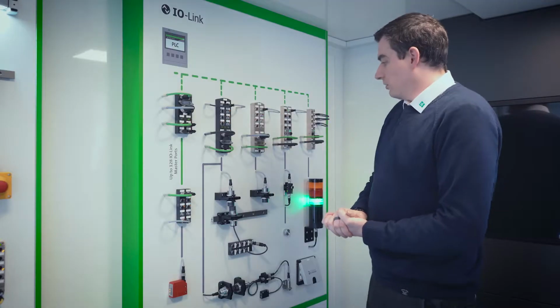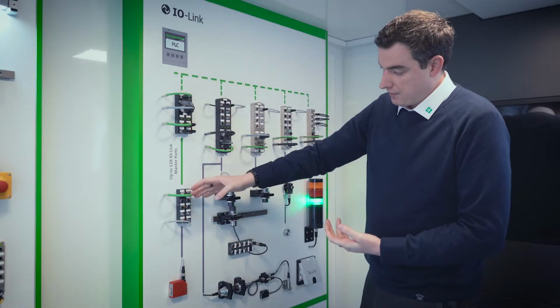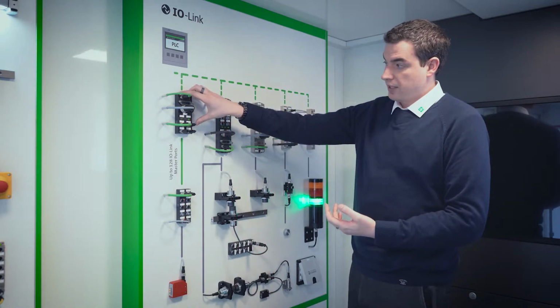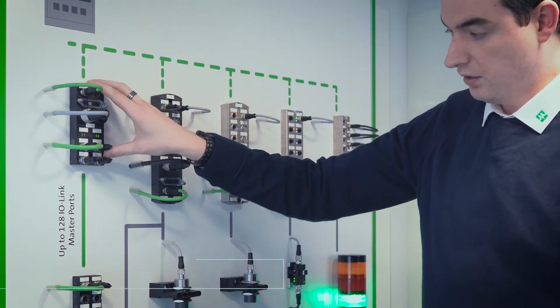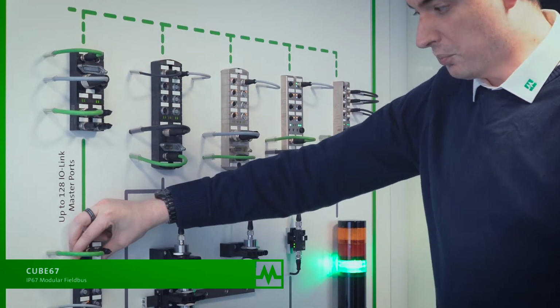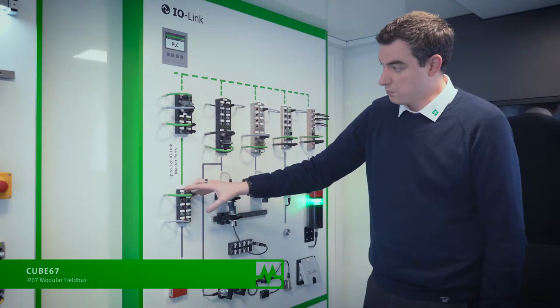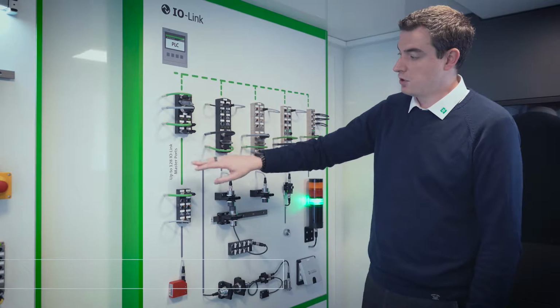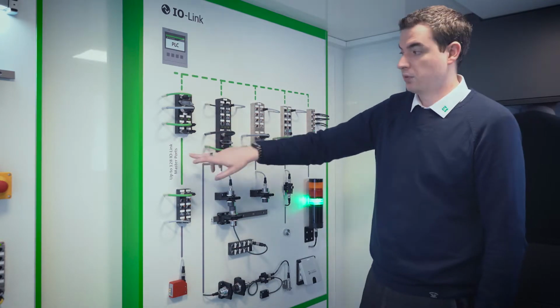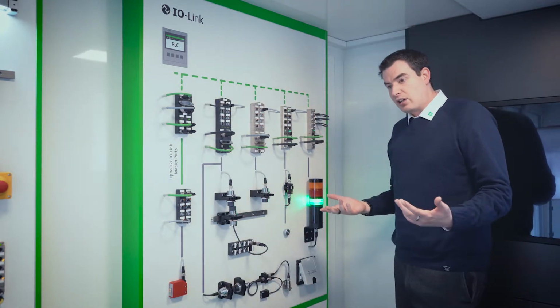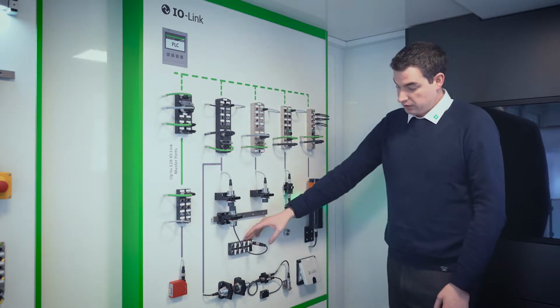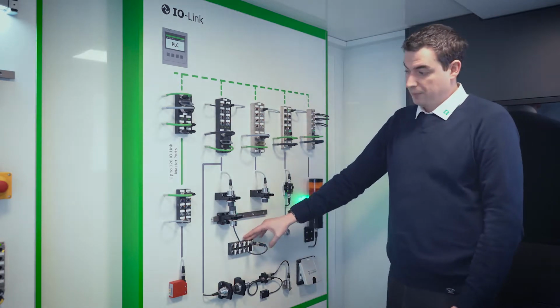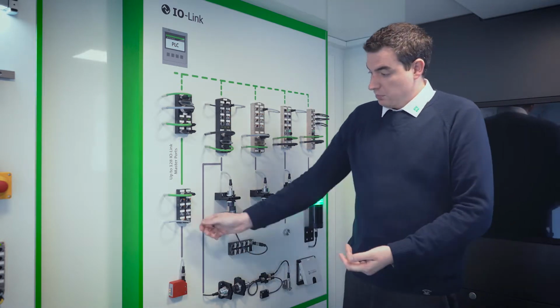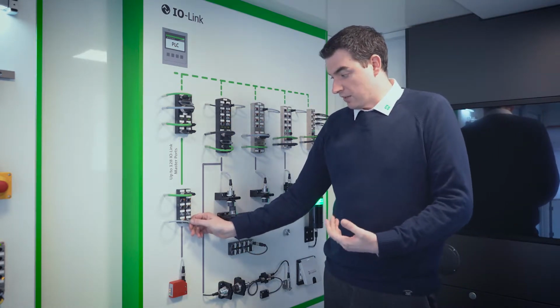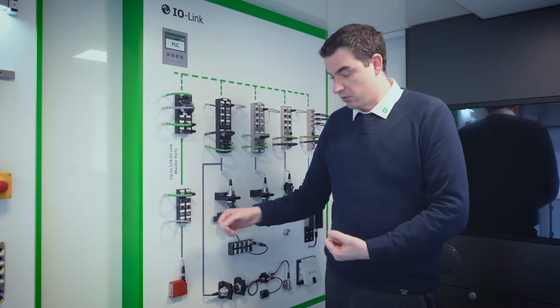With our IO Link products, we have the Cube 67 range, which consists of a bus node or master and then slave I/O points. Now, if you maxed out the Cube 67 system, you can have up to 128 IO Link master ports, which enables a lot of sensor configuration or a lot of I/O expansion in the case of hubs. For me, personally, as a commissioning engineer background, that spare port is the ultimate flexibility.